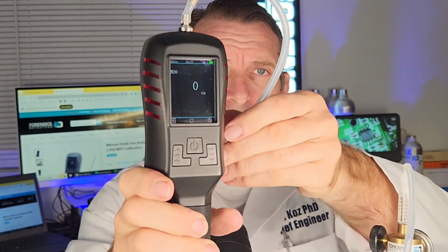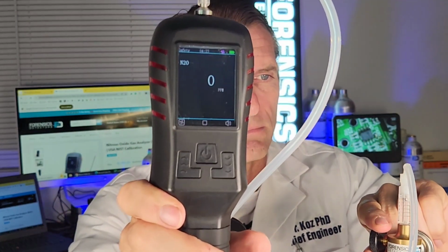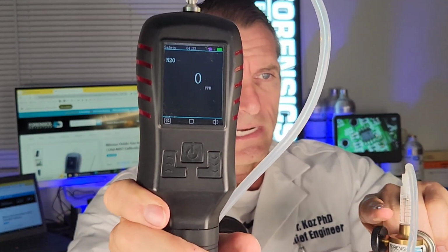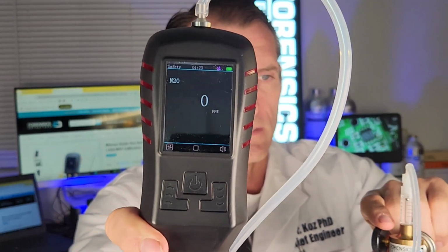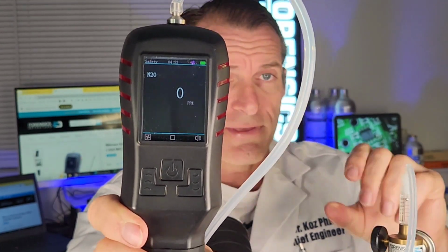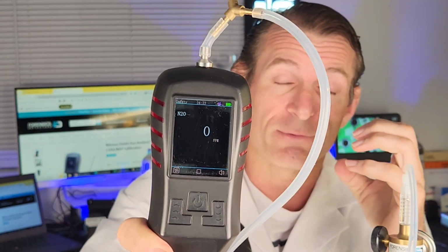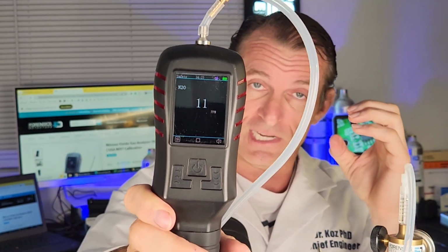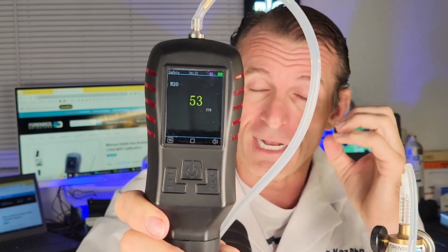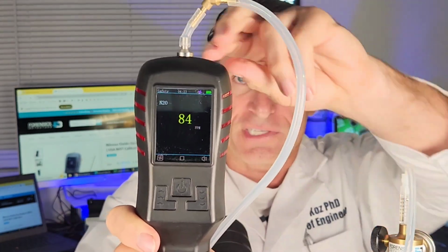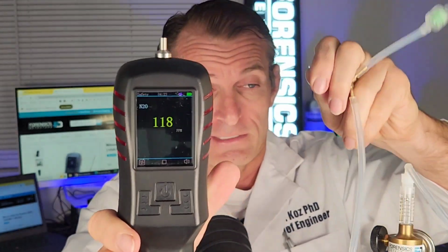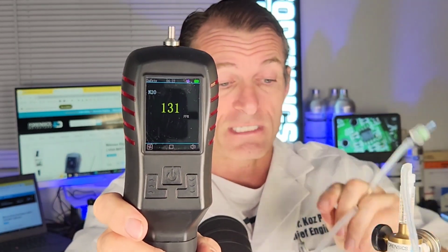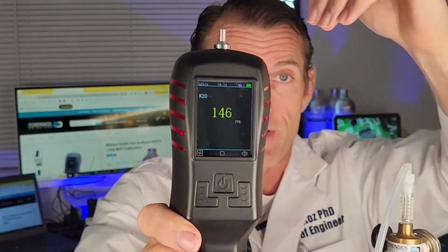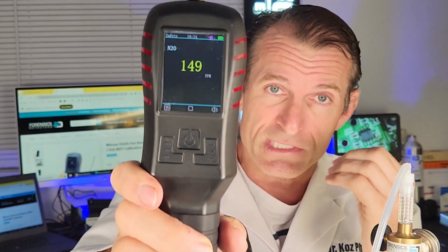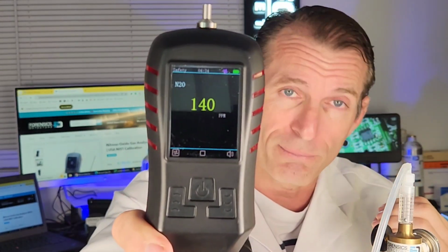So what do? We're going to turn on the pump, the micro pump, and we're going to release some nitrous oxide gas, and it's going to take a few seconds for it to start registering, because it has to get onto the sensor. And then the sensor is an NDIR sensor cell, folks. It's an absorption cell, very sophisticated, and it detects nitrous oxide in parts per million range, folks. Bang. You see the numbers going up, and I'm going to turn that off, take it off, and you're going to see the numbers going down now, because it's drawing now the fresh air, and it's going to reset the sensor signal going towards 0 parts per million.